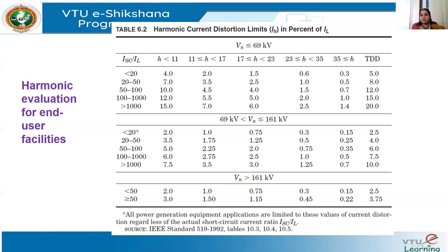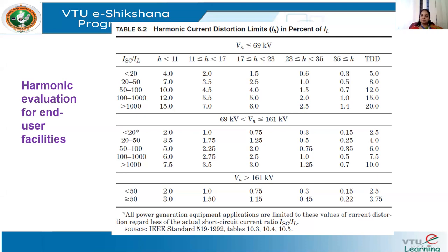We have TDD limits for every range of short circuit ratio: less than 20, 20 to 50, 50 to 100, 100 to 1000, and greater than 1000 — all given for different voltage levels. As the short circuit ratio increases, the TDD can be increased further. These limits are proposed by IEEE standard 519-1992. Now we need to see how to evaluate the short circuit current.